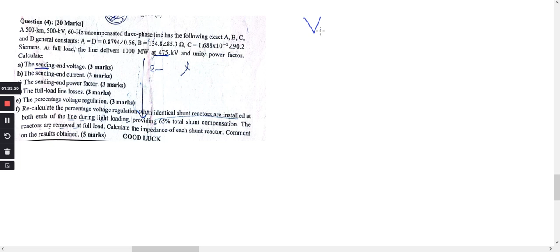Can you calculate the receiving end current? It's the power divided by root 3 times V. I forgot to divide this by root 3, so divide this number by square root of 3, put it over here: root 3 times the receiving end V times the power factor.